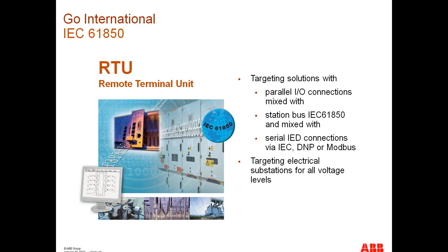Here I have a separate slide dealing with the IEC 61850, which is the latest norm, and it is an international norm. This is a norm dealing with communication protocols, and it has the idea that one system can be built out of different devices coming from different vendors but speaking the same language. So it is the target solution. They are built with the 61850, with parallel input and output connections mixed with a station bus, as well as serial IED connections via different protocols at all voltage levels in the end. So you have a communication independent from the vendor.